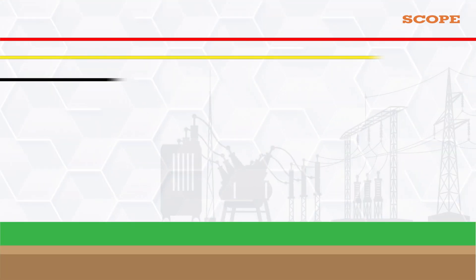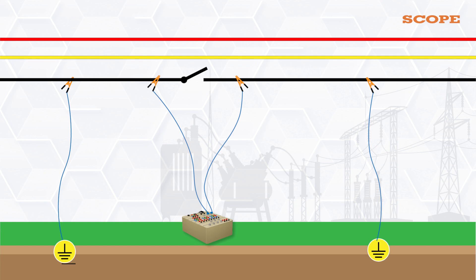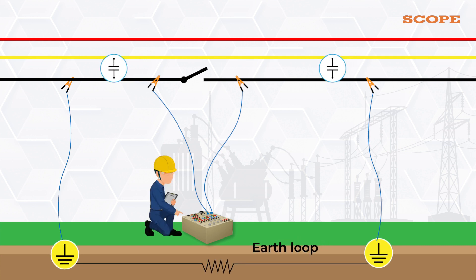But when the CB is grounded from both sides, it creates an earth loop parallel to CB contacts, posing a real challenge to measuring both closing and opening times along with bounces and capturing the signature of dynamic contact resistance.